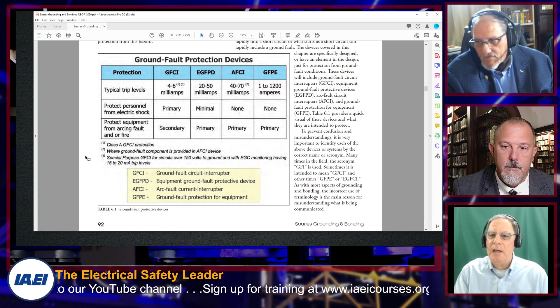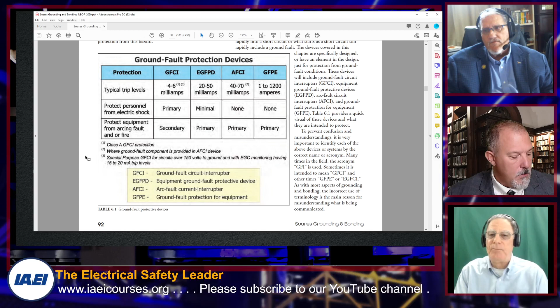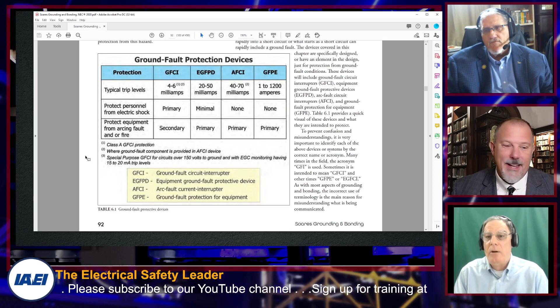Oh, and by the way, that's because you're grounding the person and mitigating potential differences. Exactly. So you achieve that with the equipment grounding conductor that bonds everything together until you get to the service or separately derived system, which then grounds everything down. So that green wire does both grounding and bonding.